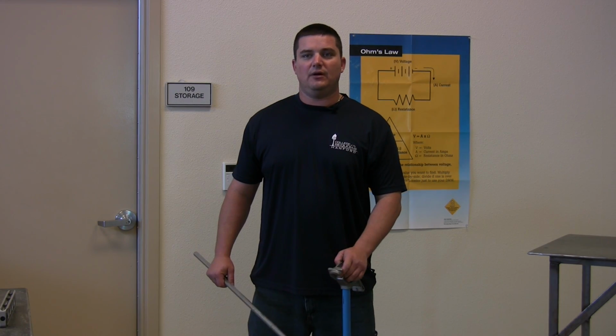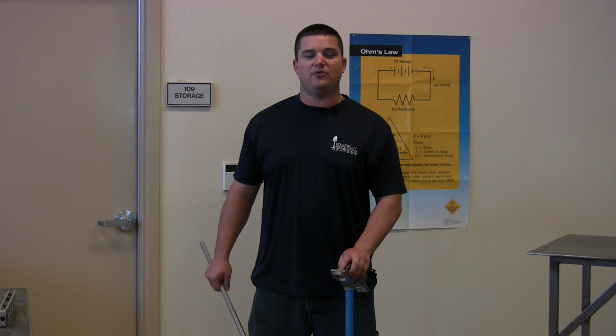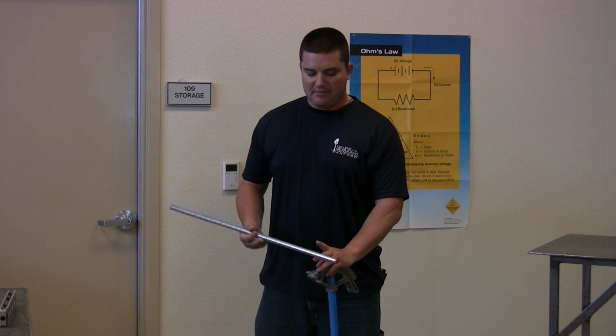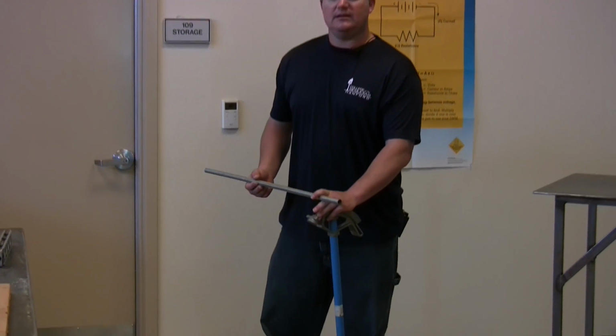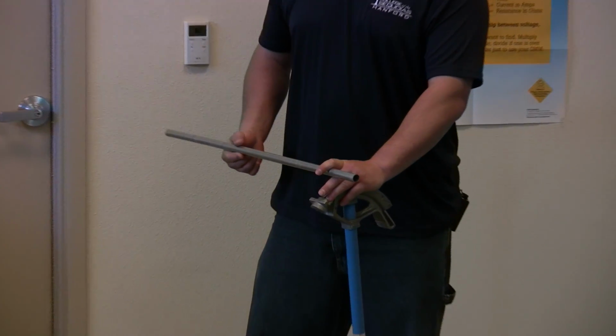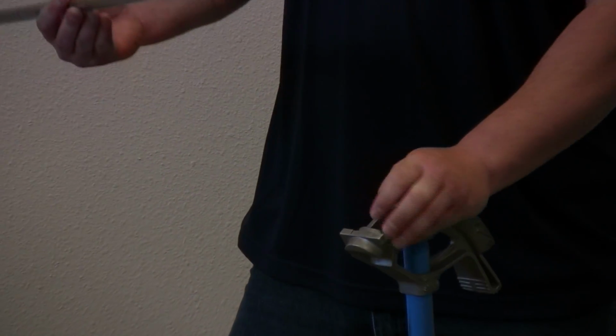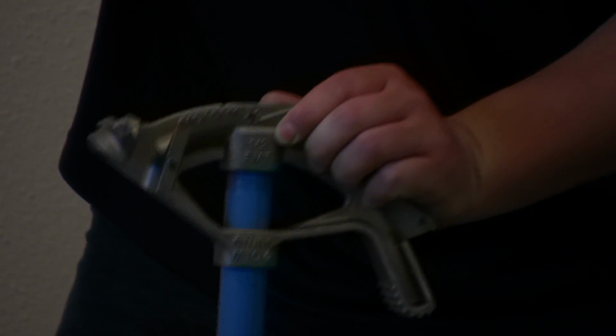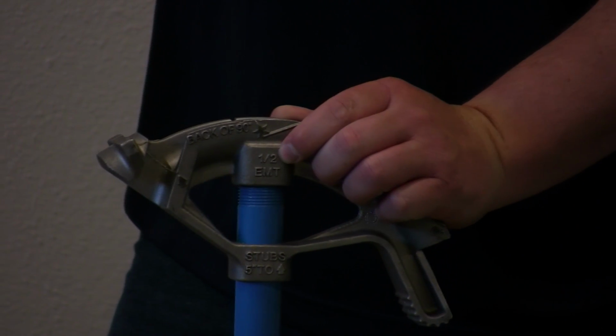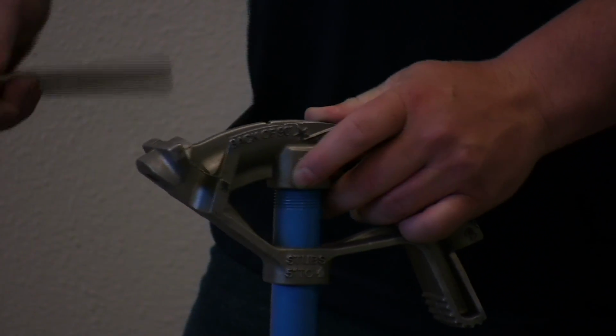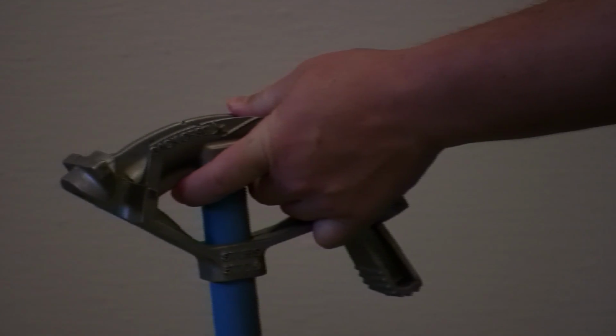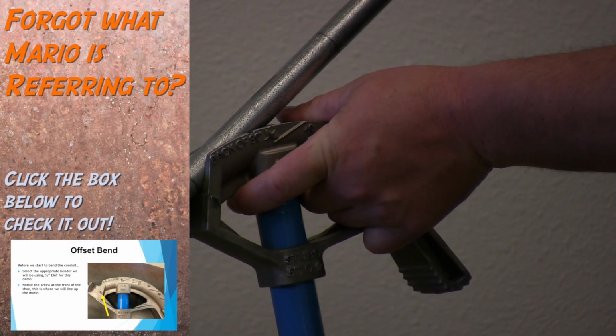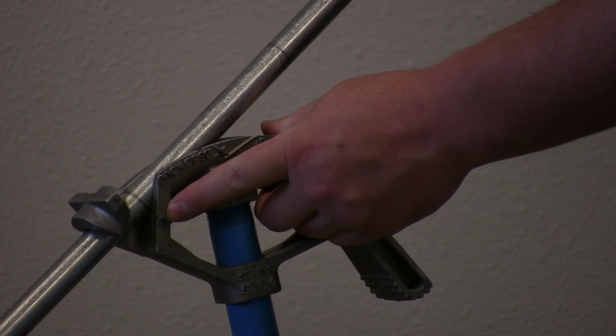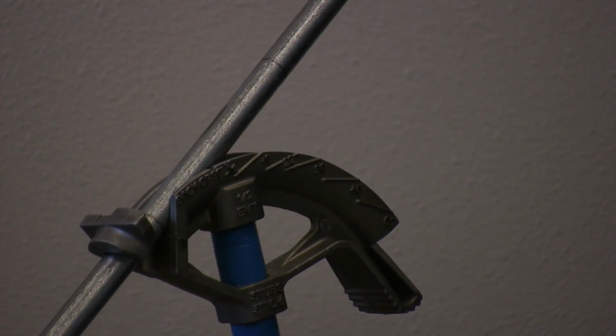So now with our conduit marked, the next step is making sure that we use the appropriate bender. We are actually going to be bending 1/2 inch EMT conduit. It's a thin-walled conduit, typically used in commercial applications. So we need to match it to our 1/2 inch EMT bender, and it's stamped on top of the shoe. So now that we know those two items match, what we do is put our A mark at the arrow of the bender. So once you have those two lined up, it's time to actually start to bend.